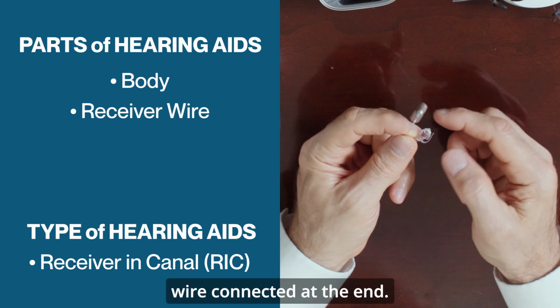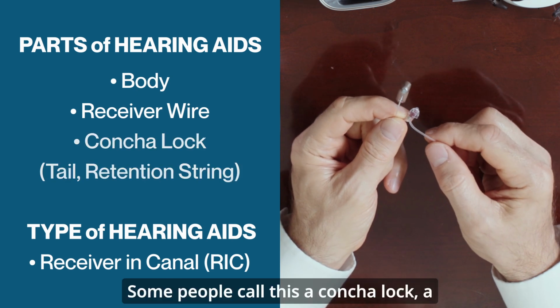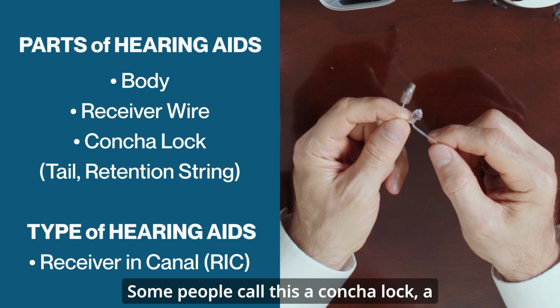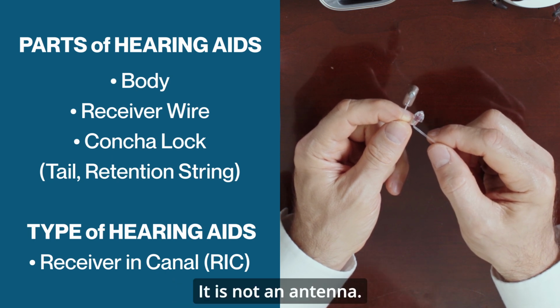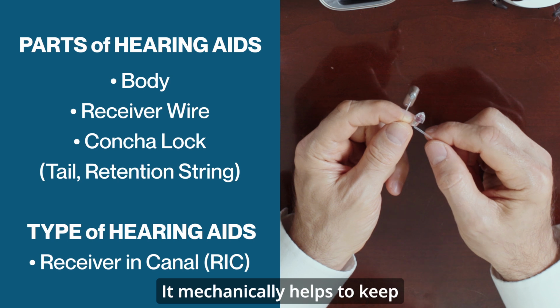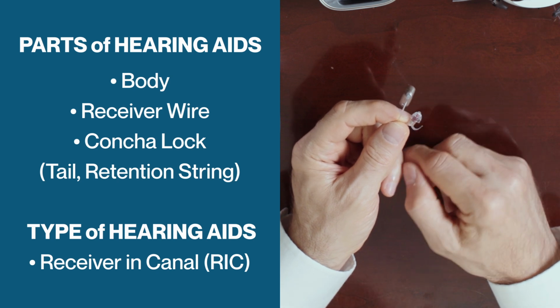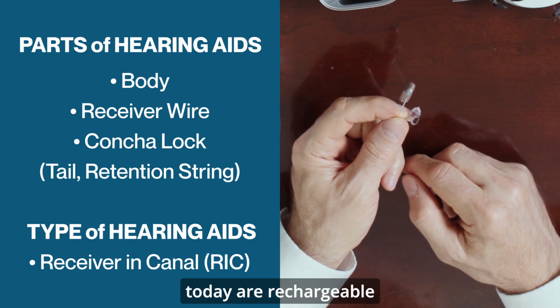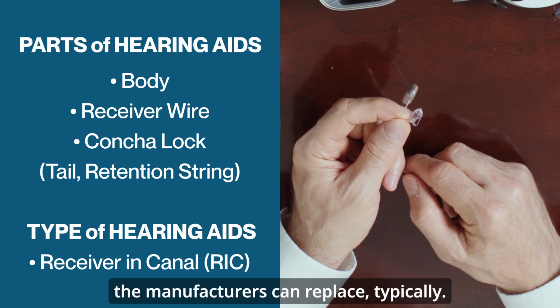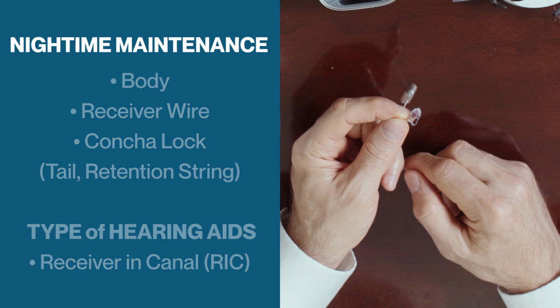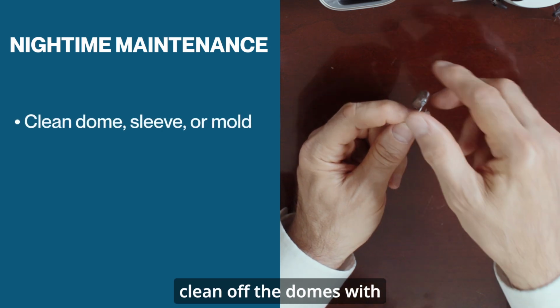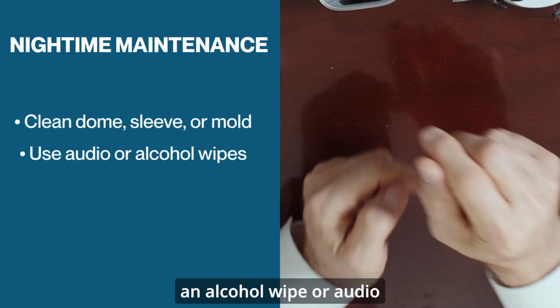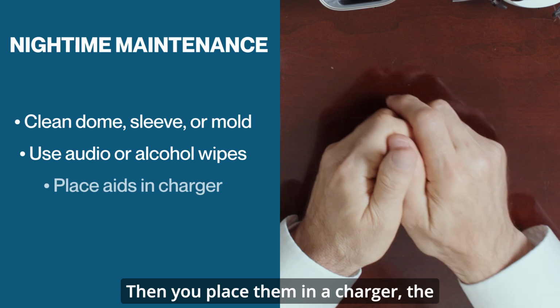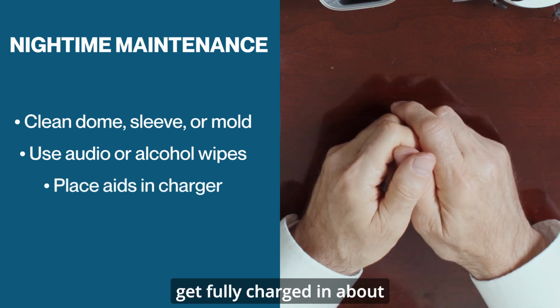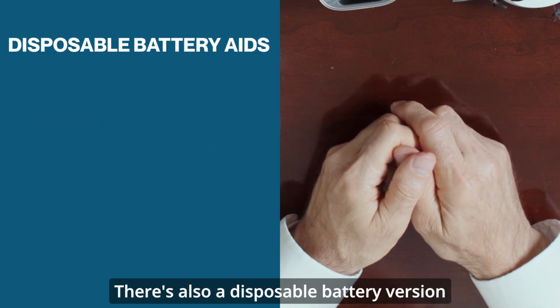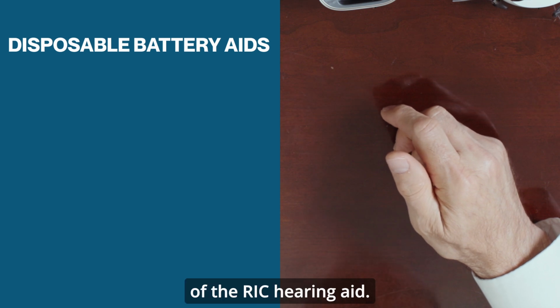There's also a retention wire connected at the end. Some people call this a concha lock, a tail, or a retention string. It is not an antenna. It mechanically helps to keep the hearing aids in the ear. Most receiver in the canal hearing aids today are rechargeable with batteries that only the manufacturers can replace, typically. When you take the aids out at night, you clean off the domes with an alcohol wipe or audio wipes. Then you place them in a charger, the lights go on, and the aids get fully charged in about 3 hours. There's also a disposable battery version of the RIC hearing aid.